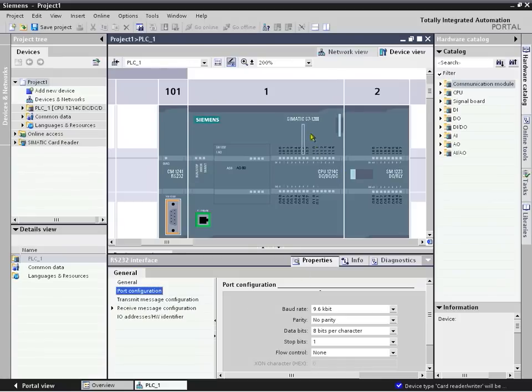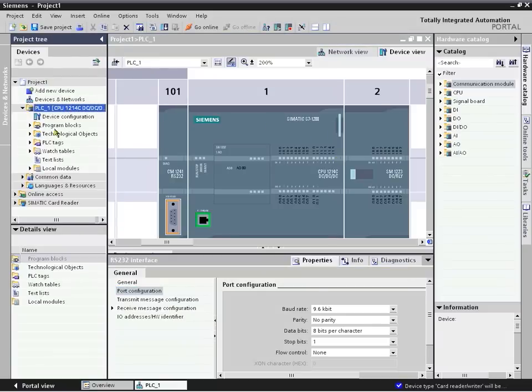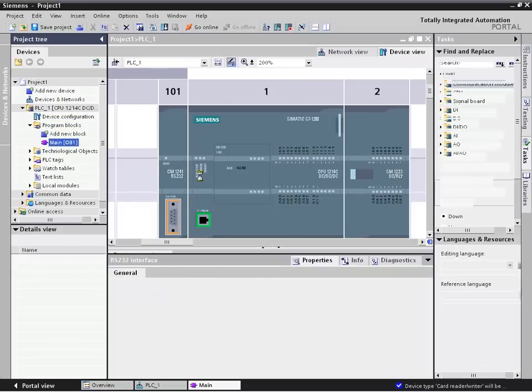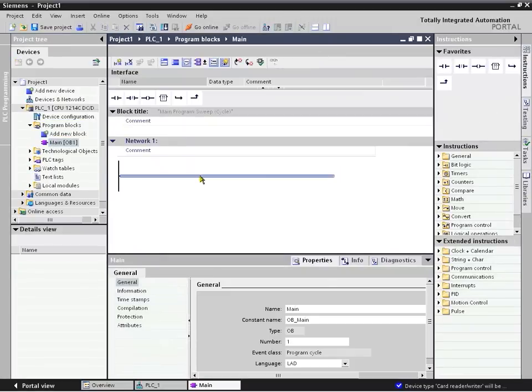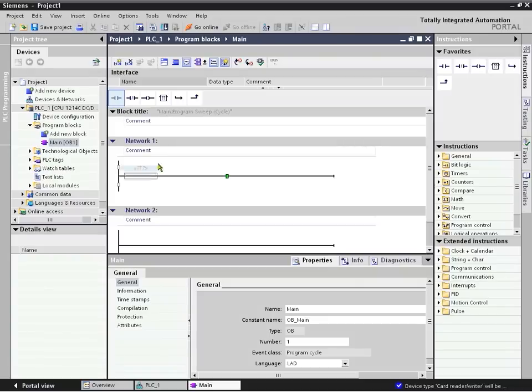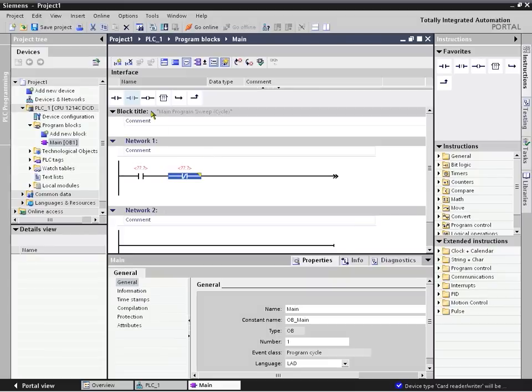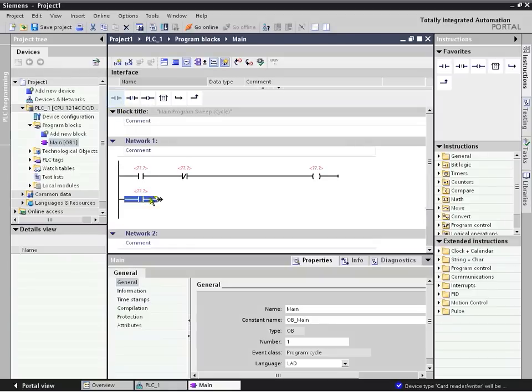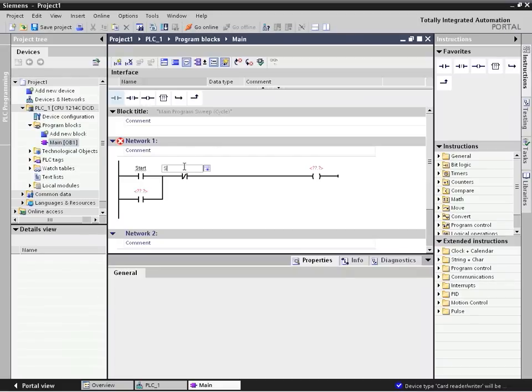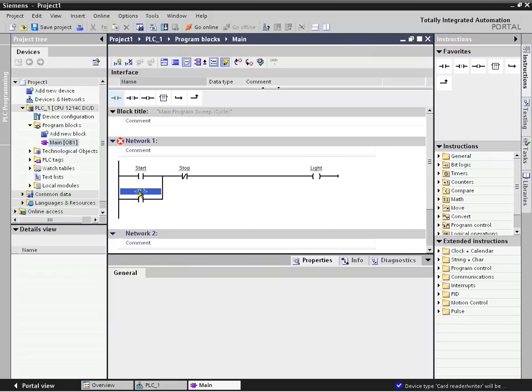So to get started with our programming, we're going to go right to the main programming block and drag and drop our logic in. So we're going to put a normally open for the start, normally closed for the stop. We're going to put our output coil there, and then we're going to put our seal-in circuit. It's all drag and drop. There was no typing. There was no other editors. And from this point, I'll just give it my own labels for tags. I'm not worrying about any type of address convention or syntax that is necessary. And our seal-in will be this normally open contact of the same output. So there's our traditional start-stop seal-in circuit.